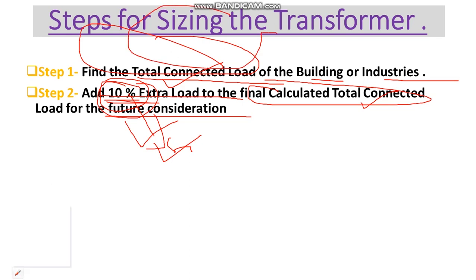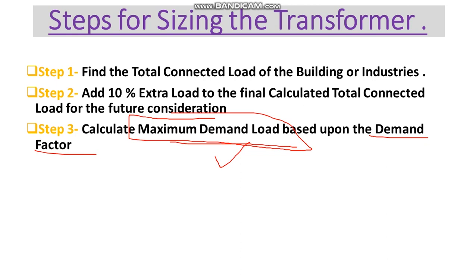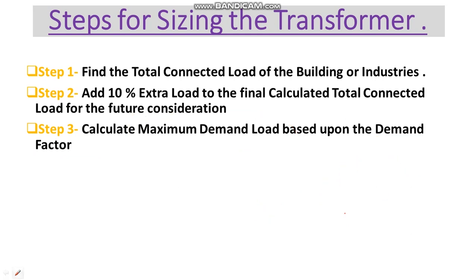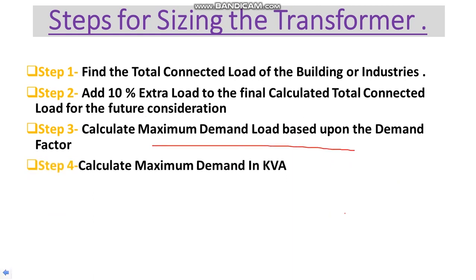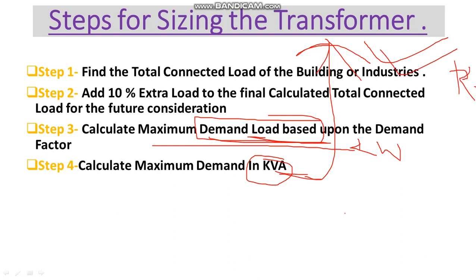In Step 3 we have to calculate the maximum demand load based upon the demand factor. We will not always switch on the whole total connected load — for a commercial building we generally consider 80% of the load is on at any time, while 20% will be switched off. In Step 4, if our calculated maximum demand load is in kilowatts, we have to convert it into kVA, which is apparent power, because our transformer is rated in kVA.